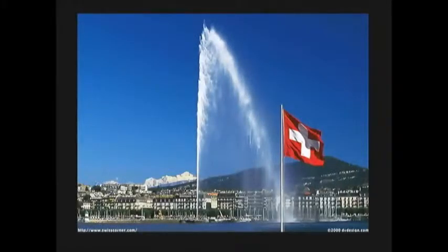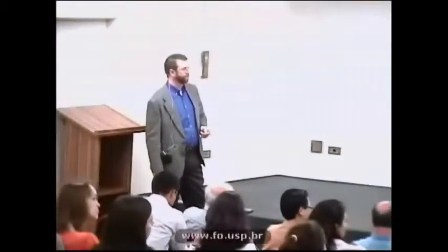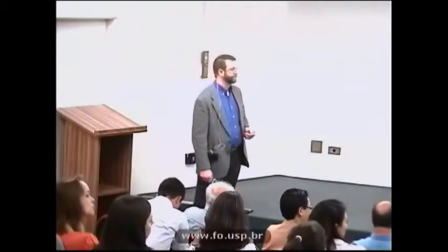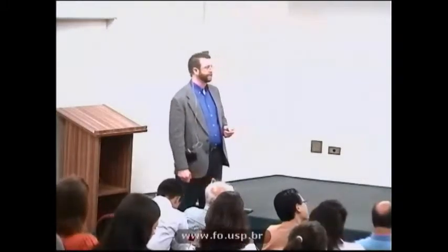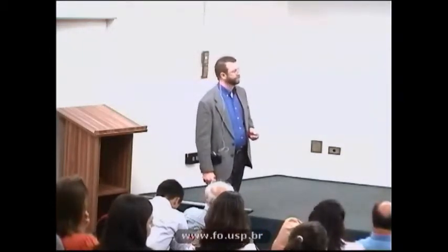Jason, in many labs here in Brazil, we have chewing simulators. They are very popular here. And it's always a question of the frequency that we are using. We can set the load very easily within the range that you showed, but the frequency is always a question because we have the pressure of time to finish the thesis. So the students are always trying to use a higher frequency to get the same number of cycles faster. How should we deal with that? Should we reduce the frequency and spend more time, or can we increase the frequency and do our experiments faster?